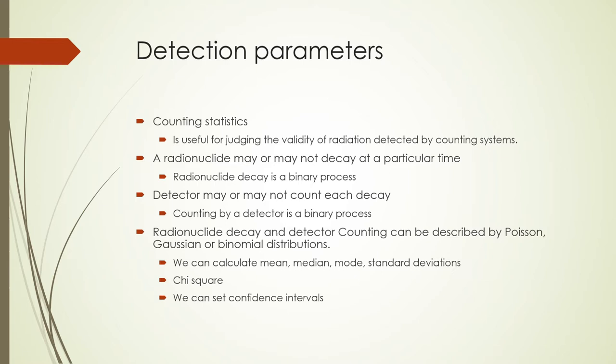Because of the random nature of these binary outcomes, they can be described by a probability distribution function. There are three probability distributions relevant to these binary processes: the binomial distribution, the Gaussian distribution, and Poisson distributions. Based on this, we can set up the detector so that we can be sure it is counting radionuclide decays correctly. Once decays are counted, we can obtain mean counts, standard deviations of counts, the errors in counts, and so on. We can even determine if the counts are random by using chi-squared analysis.